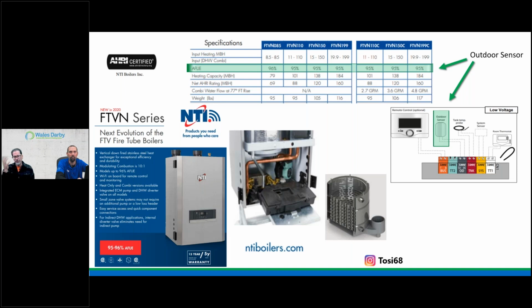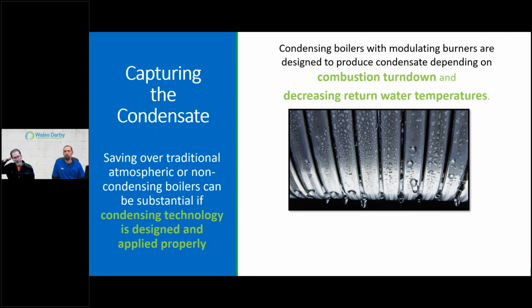But again, just showing you this photo here, that's a stainless steel heat exchanger. There are different manufacturers, different styles, but it's engineered to be in an environment of an acid. Basically, our flue gas products want to naturally leave, we're fan assisting it, but we want it so cool that it doesn't get a chance to leave, because that's dollars. Think about that. Anything that's a byproduct of fossil fuel is dollars spent. So if I can reclaim it, I'm even greater for the dollar I put in for energy use, okay? So this is it, capture the condensate, right?